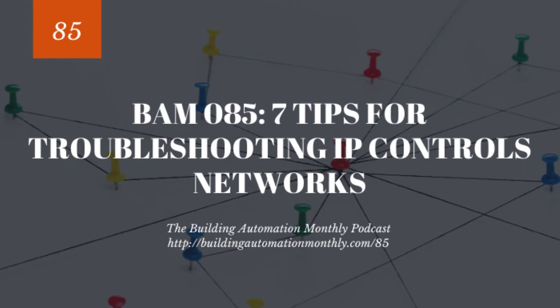So you've got this IP control on the chiller, you've got an IP control on the air handler, and the air handler's valves are driving a reset maybe on the chilled water set point or something like that. And wouldn't you know, someone decided to change a route, or someone decided to put up a firewall or some sort of proxy or something, and now it's filtering traffic and blocking that traffic, and all of a sudden the network connections are dead. So therein lies the rub.